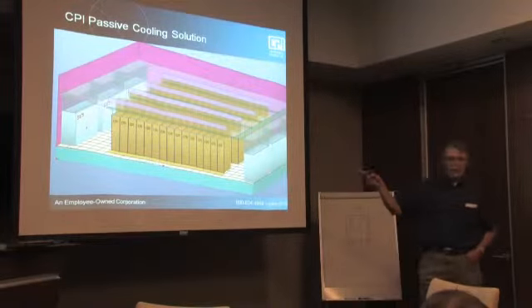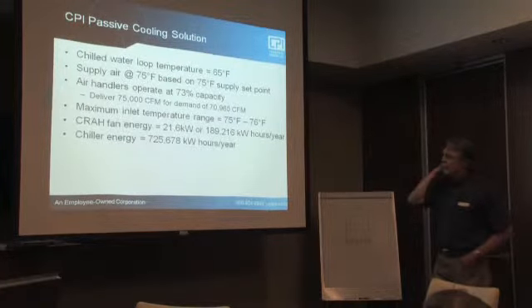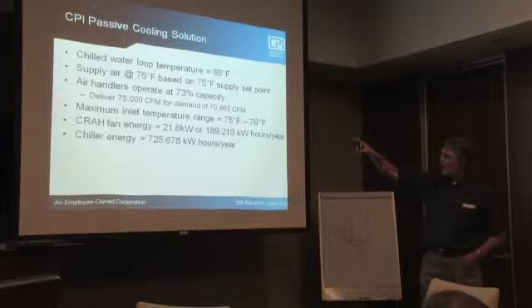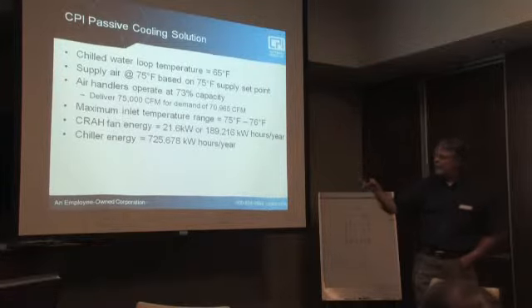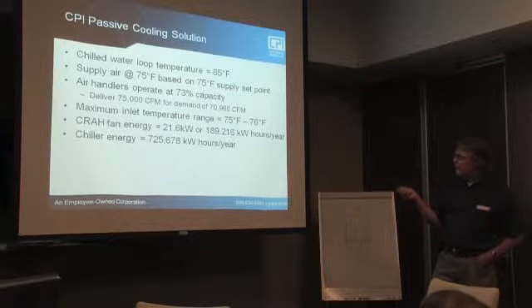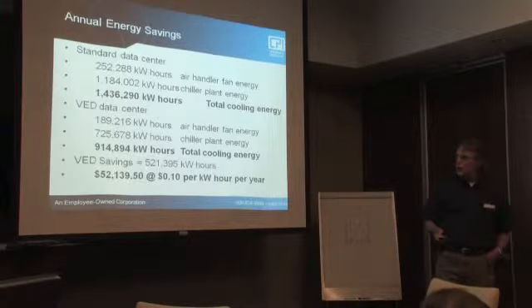Comparing that to a VED data center: we raised the chilled water loop temperature to 65 degrees, moved the set point from return to supply and raised it to 75 degrees. Air handler capacity dropped to 73 percent — only 75,000 CFM needed to meet the server demand of 71,000 CFM. Server inlet temperatures range from 75 to 76 degrees. Fan energy is down to 189,000 kWh and chiller plant energy is 725,000 kWh.